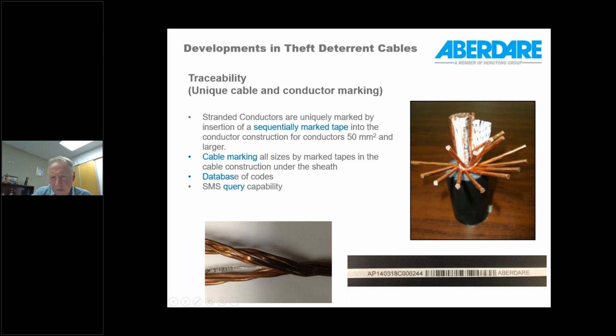the right equipment. Here's a picture of a medium voltage cable with water blocking. You see the white is the water blocking, and in the inner portion you can see bits of the barcode. That is the barcoded tape which is applied to the conductor. At the moment, the limit is at strand constructions of more than 7 wires. Just purely a physical constraint at this particular point, and all larger sizes can easily be marked with this tape.